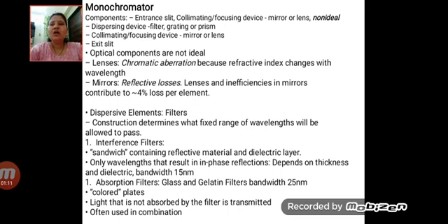They are used because these are the most important devices in resolving the polychromatic radiation into individual wavelengths, or into monochromatic radiation. To achieve this, entrance and exit slits are used. The width of the slit plays an important role in the resolution of polychromatic radiation. The narrower the slit width, the narrower the bands isolated. However, it limits the intensity which reaches the detector.